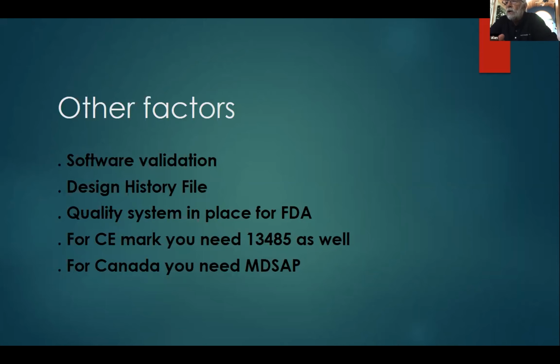For a CE mark, you're going to need the 13485:2016, and that's going to be now under the MDR, Medical Device Regulation for the European Community. For Canada, you will need the MDSAP, which is the Medical Device Single Audit Program. It includes the 13485. It also includes the FDA GMPs and Brazil and Japan. So Canada is the only country at this time that is requiring that you have MDSAP certification in place.